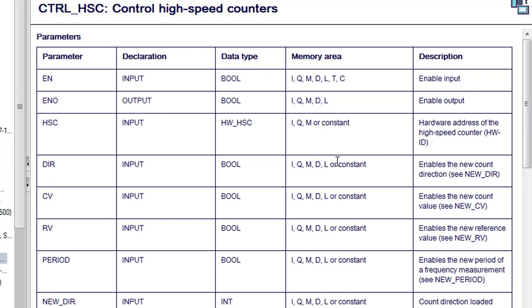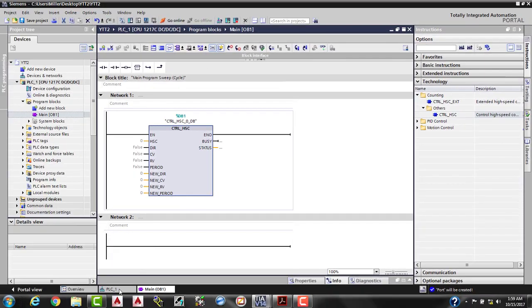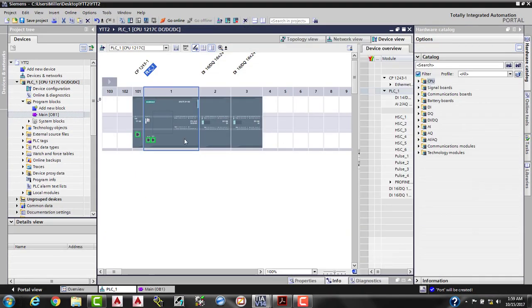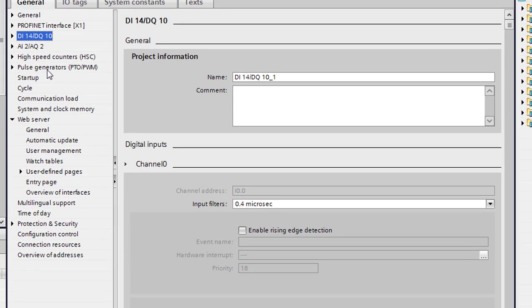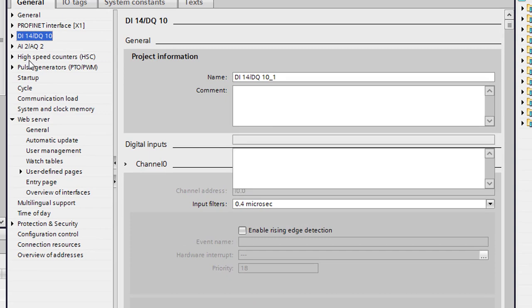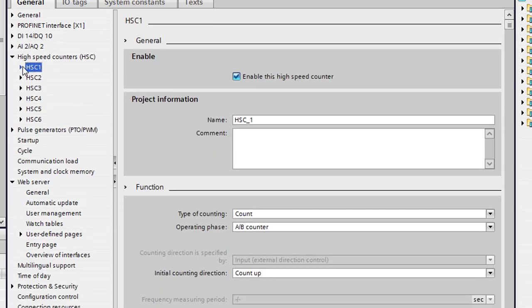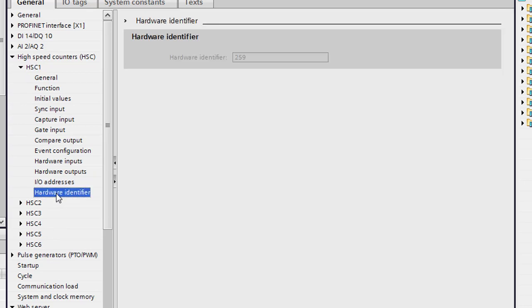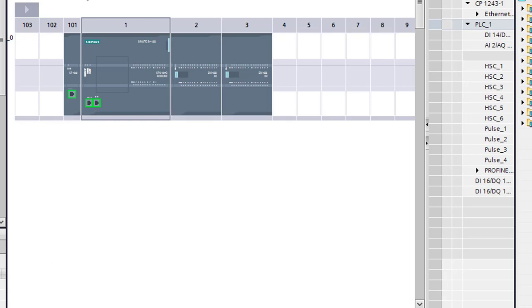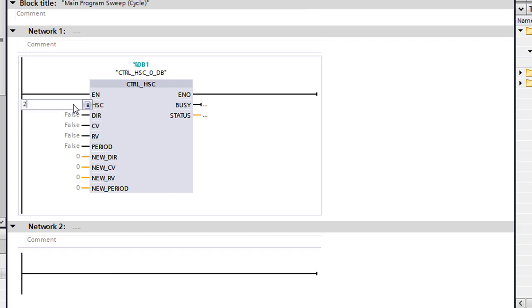It should pull up right to the counter you're on. And if we go down here and look where it says HSC, which is right here, input, this is the hardware address of the high-speed counter. So where is that again? We need to go back to the PLC. We'll go ahead and lift the page back up here so we can see what we're doing. We're going to select properties. We're going to go back to the high-speed counters, expand it. We'll expand high-speed counter number one, and hardware identifier is right here. So we want 259. So we'll go ahead and go back to our organizational block. We'll go here. We'll just type in 259 and press enter.